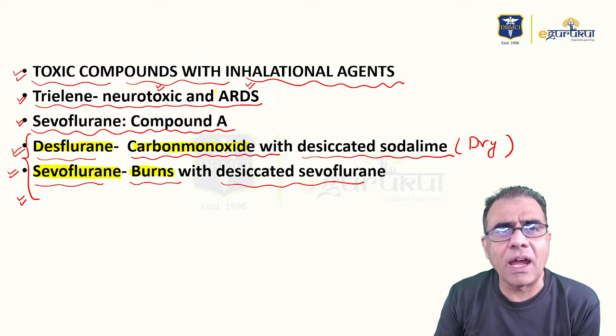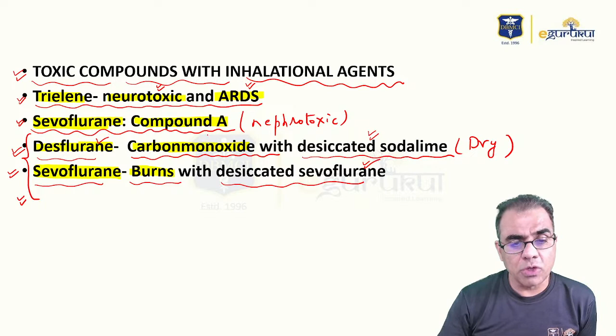However, the agents which are available today can also react with soda lime to produce toxic compounds. For example, sevoflurane produces a toxic compound called compound A, which is a nephrotoxic agent. Then with desiccated soda lime, that is dry soda lime, desflurane can produce carbon monoxide and sevoflurane can cause burns. But I told you these are rare complications. So that's all about the anesthesia delivery system.